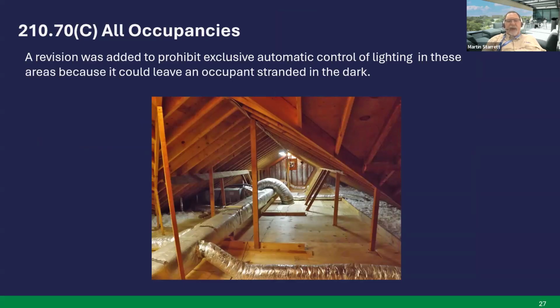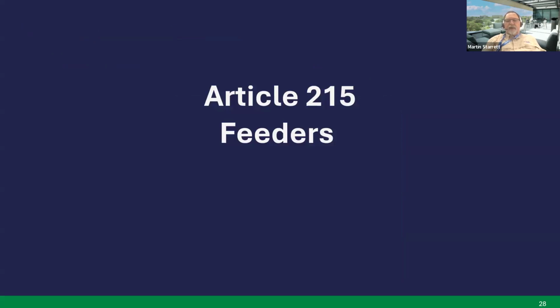210.70(C), all occupancies, lighting. A revision was added to prohibit exclusive automatic control of lighting in these areas because it could leave an occupant stranded in the dark. You could still have them, but they're going to have a manual override. Article 215, feeders.